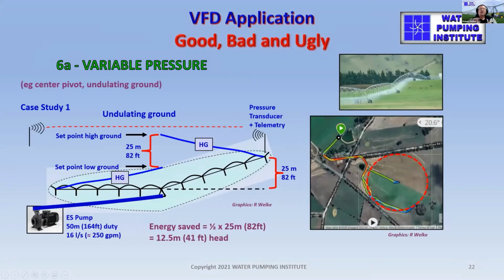But variable pressure, the classic situation might be, for example, if you've got a center pivot, and the center pivot traverses some undulating ground. And typically when it does that, you would have to configure the pump to provide the minimum residual when the end of the center pivot is at the highest point. Of course, that means when the center pivot rotates around away from that point, then the end of the center pivot will be lower. There'll be much higher residual, and that amounts to wasted energy.